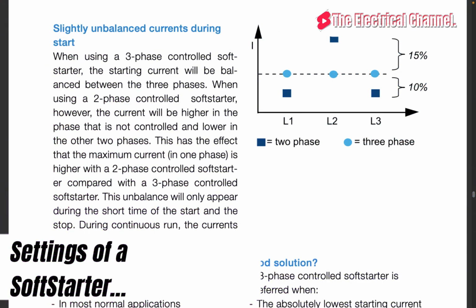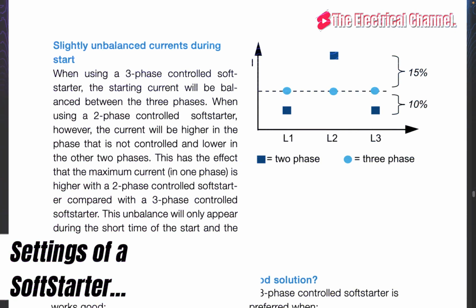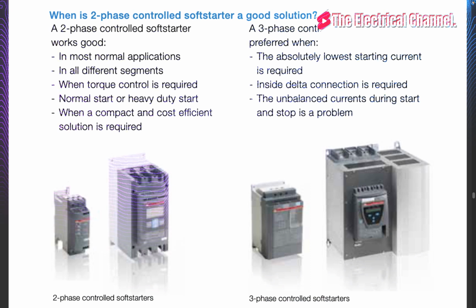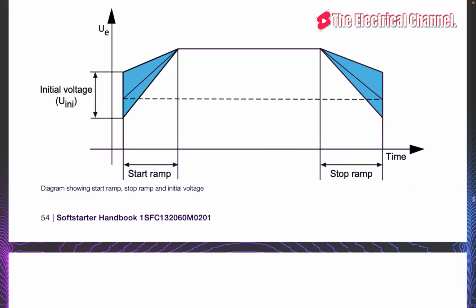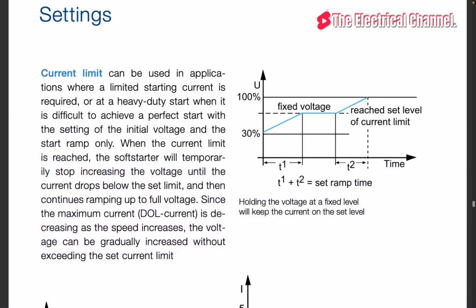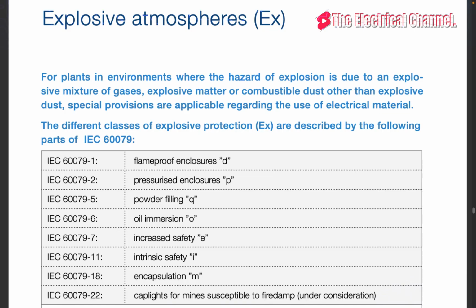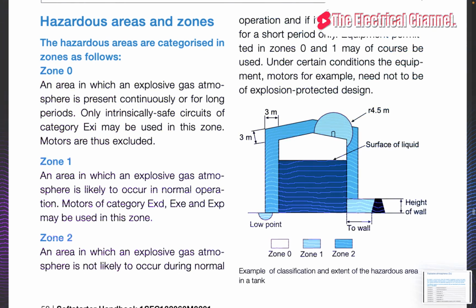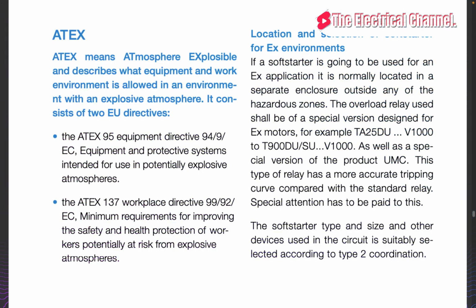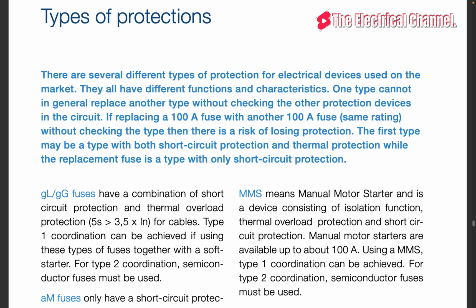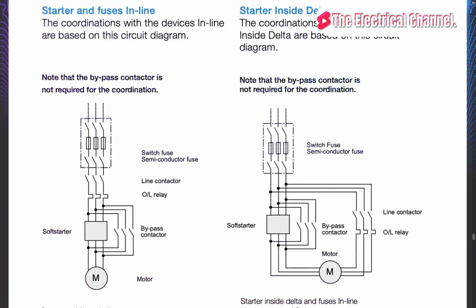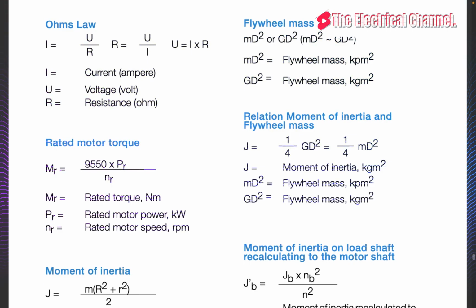A common misunderstanding is that this parameter sets start time, that is, the time for the motor to reach full speed. This is not true. The start ramp parameter only sets the time until the softstarter applies full voltage to the motor. If the motor is unloaded, the start time for the motor will probably become shorter than the set ramp time. And if the motor is heavily loaded, start time will probably become longer. If the ramp time is set to 0, the stop will be like a direct stop.